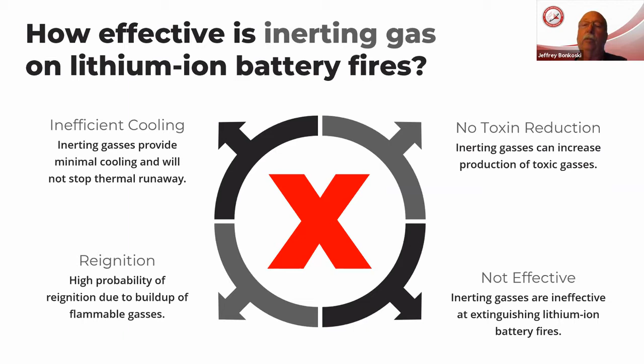The reignition - and I'll mention again that explosion in Arizona with the battery energy storage system that injured 4 firefighters - the fire protection system in that storage container was an inerting gas. Once the container was opened, oxygen entered. All the things needed were still there because the inerting gases did nothing to cool or remove those toxic vapors and flammable gases. When oxygen was present, they had an explosion again that injured those firefighters. So these inerting gases are very ineffective as well.